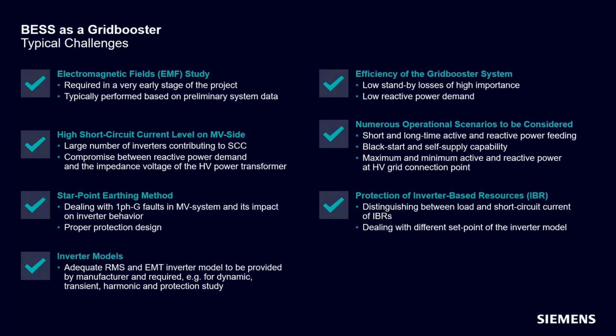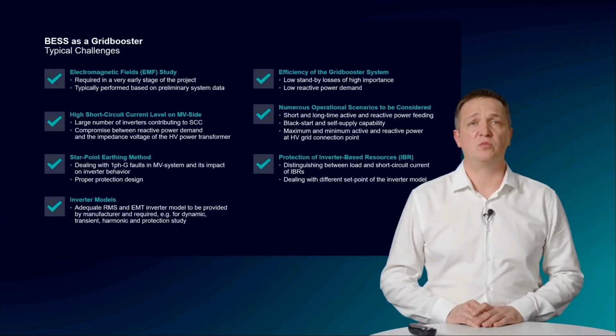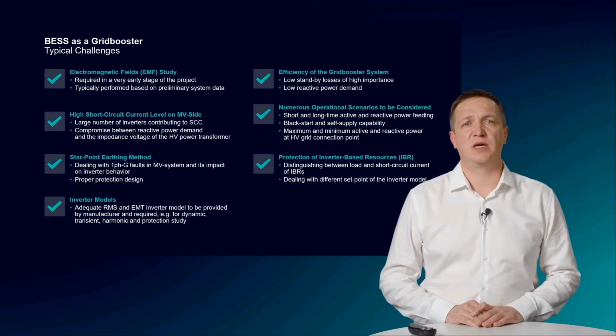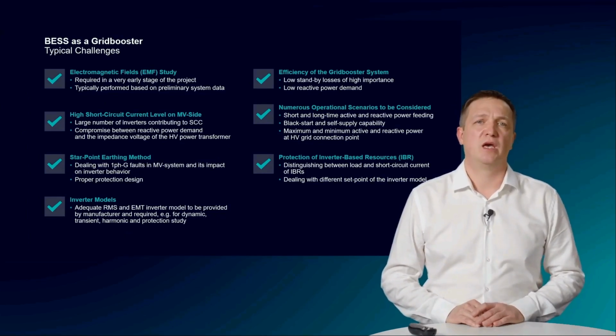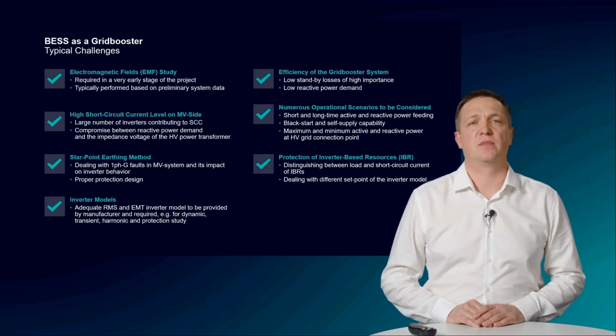When describing the requirements for energy studies and deciding on the manufacturer of the equipment, it must be assured that the simulation models are available and that they are validated within the chosen software environment. This applies for both root mean square as well as electromagnetic transient simulations. These models shall provide fault ride-through and other grid compliance features required by the respective standards and technical guidelines.